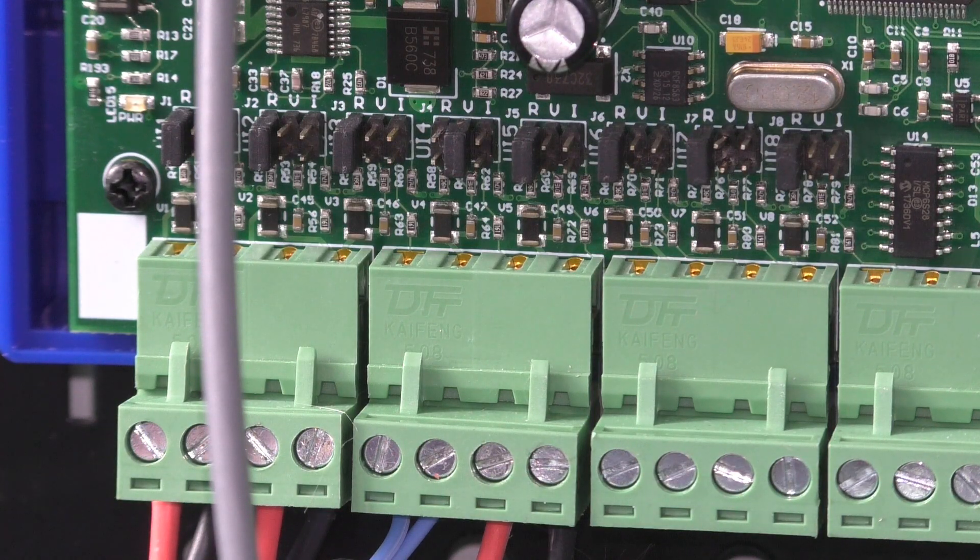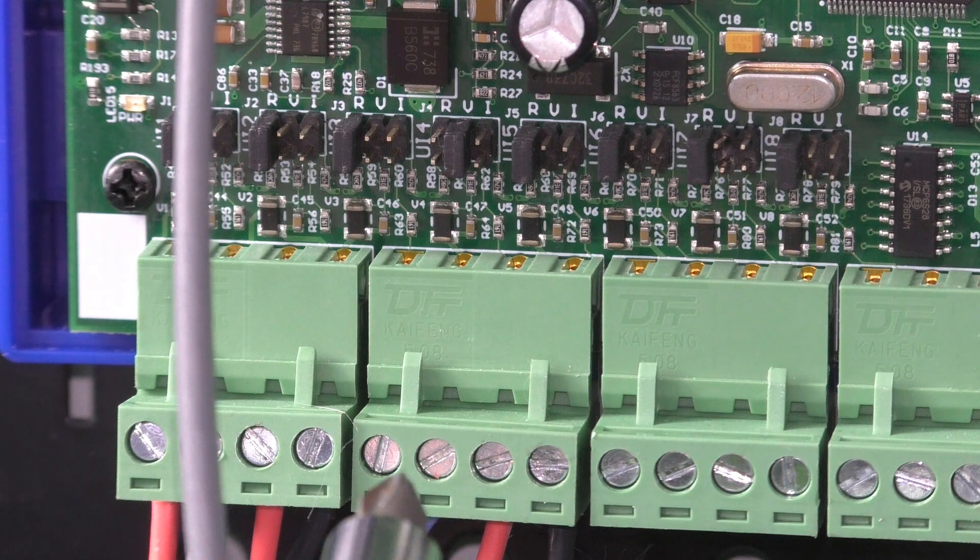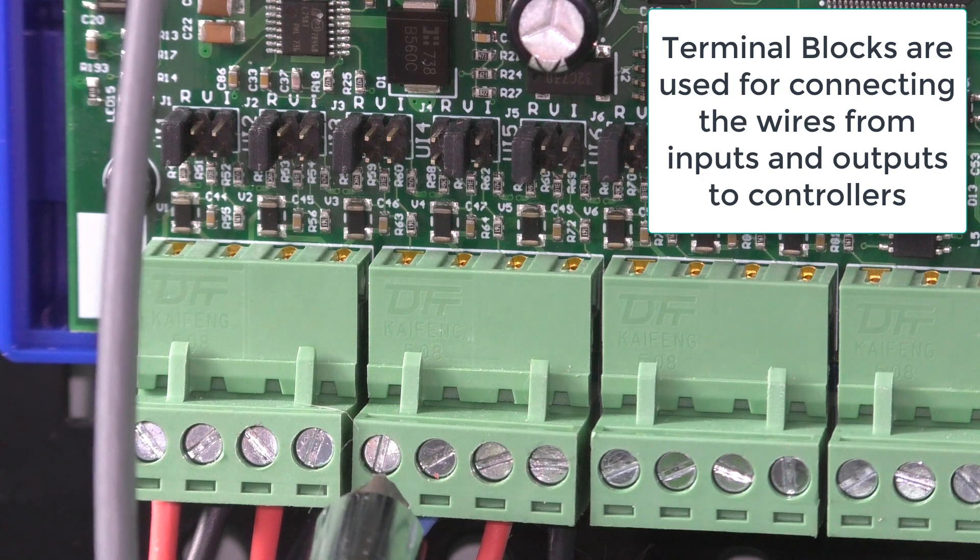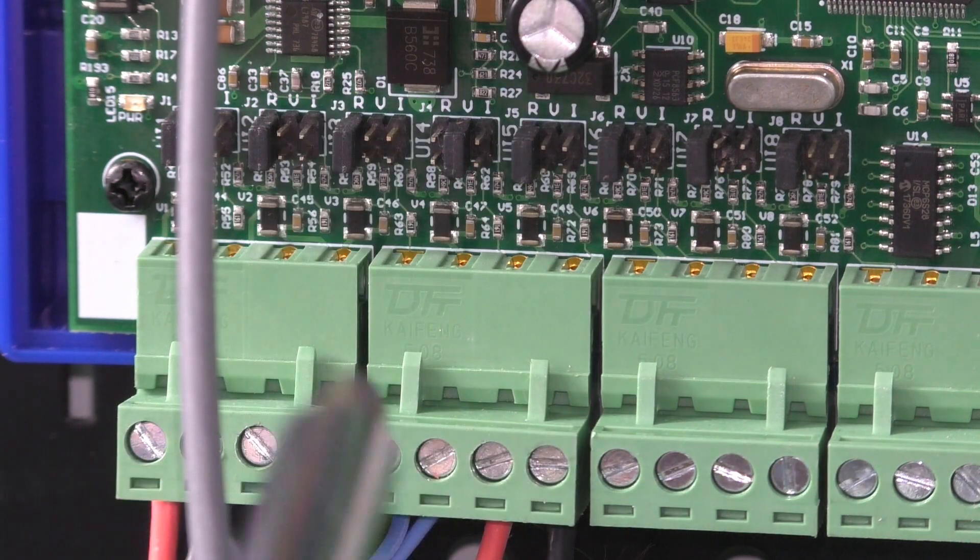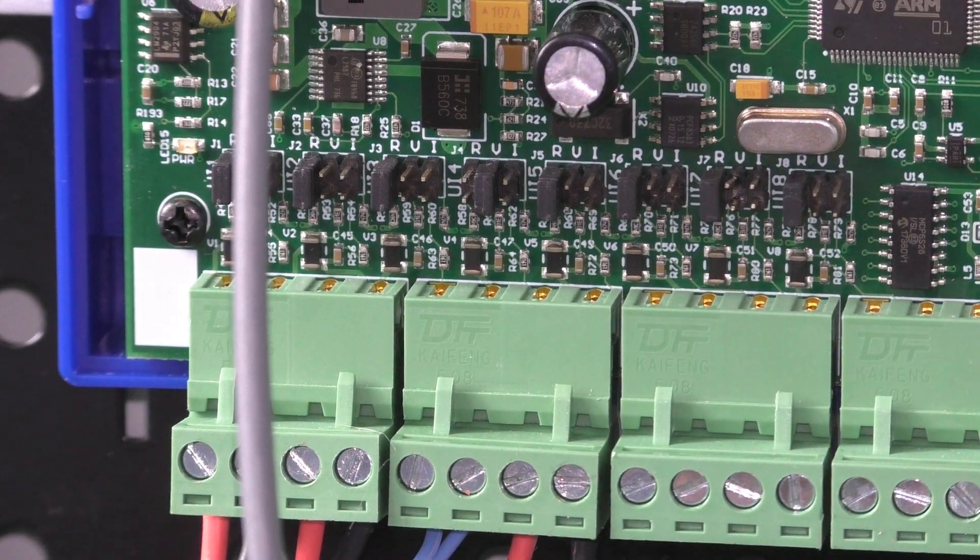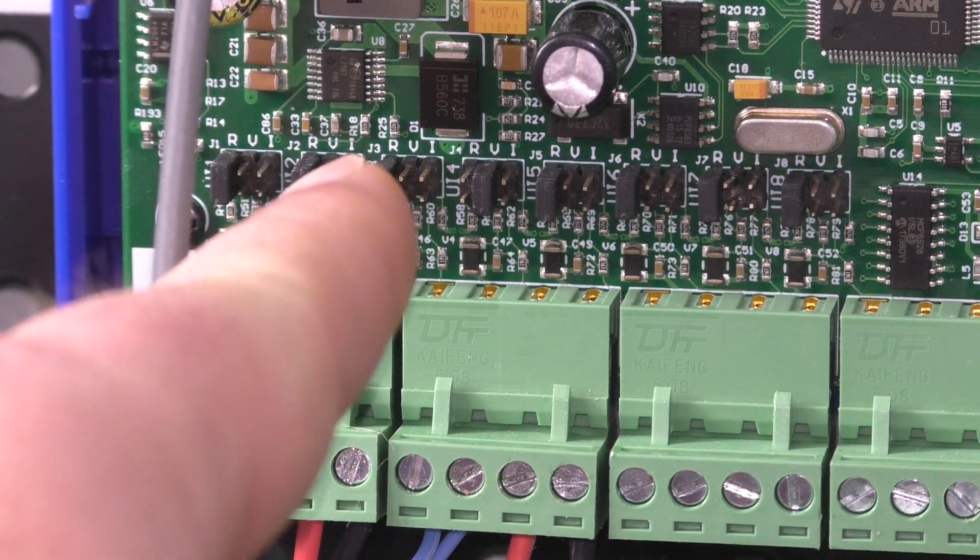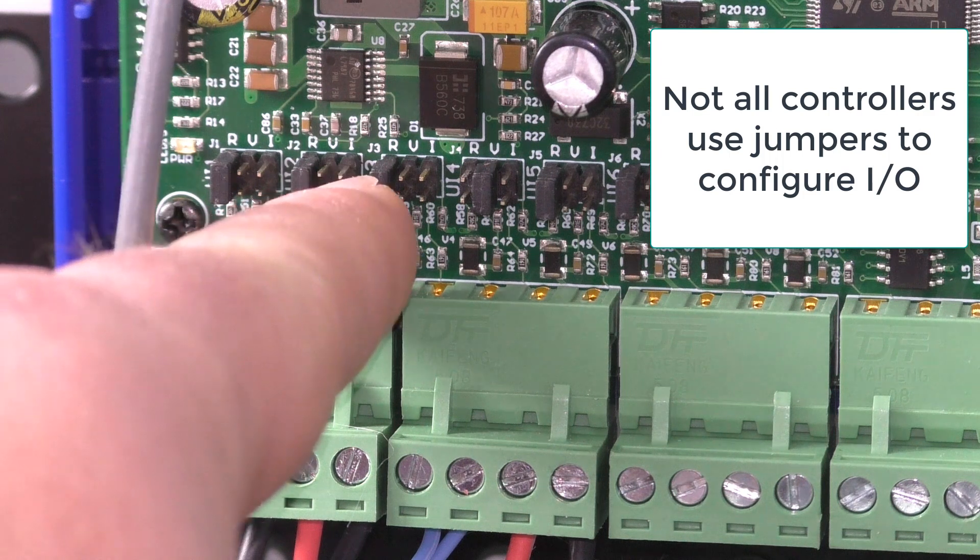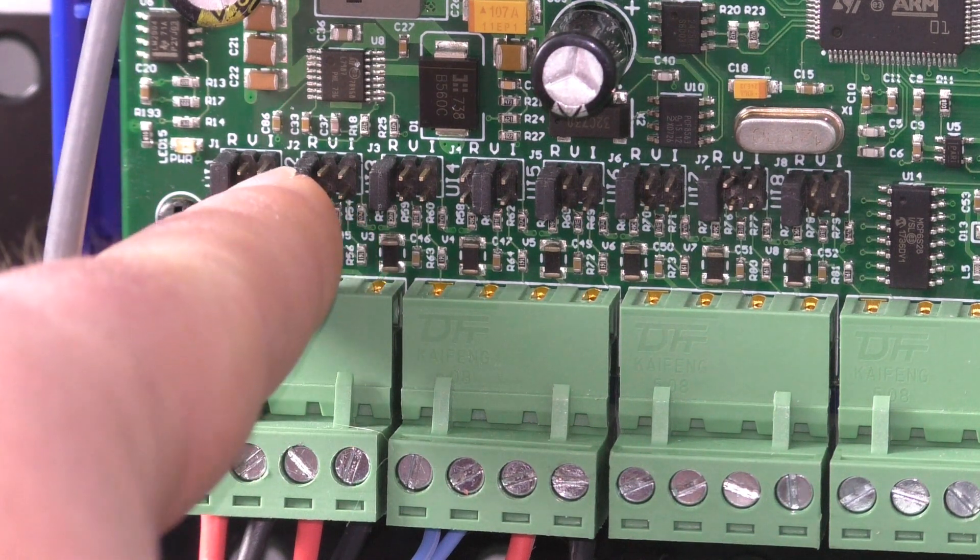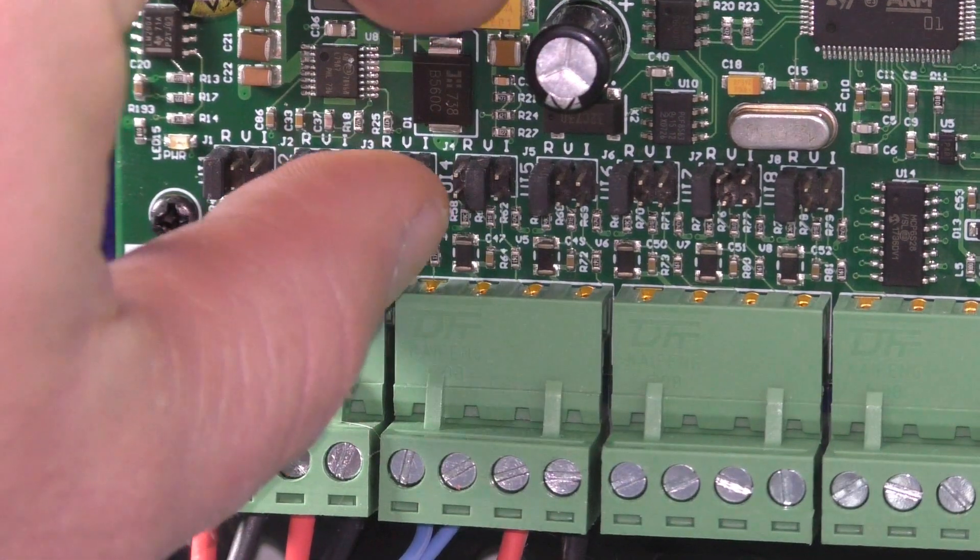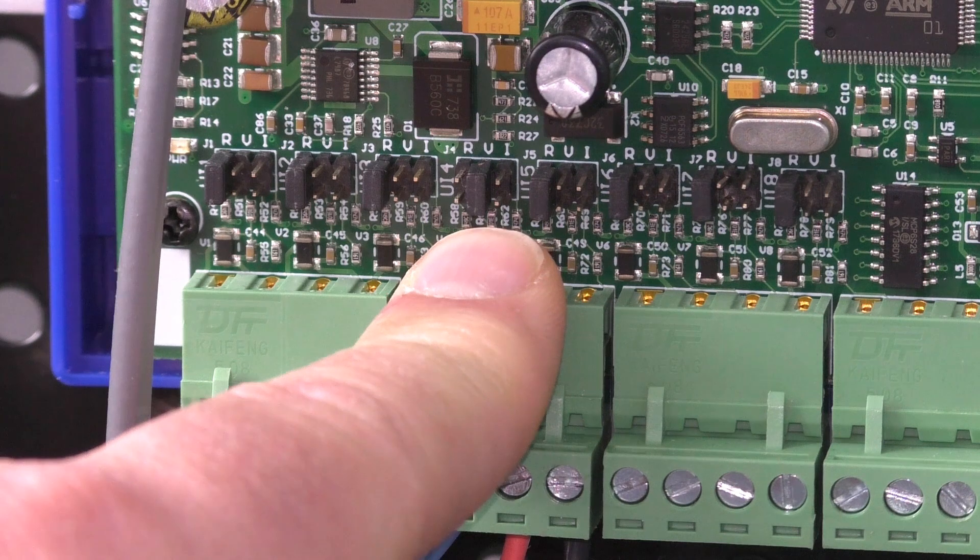What we can see is right here, we've got our terminal blocks. These are where our wires connect to, they get screwed down, you can see right there. The flathead screwdriver will go in and screw it down. We can see over here that we have jumpers. You have an R, V, and I right above the jumper—R is for resistance, V for voltage, and I for current or amperage. If we want to take a resistive input, we would switch it right here. If we want to do a voltage input, we would move our jumper. We can just pull the jumper off and plug it in. You can see I actually did that on this one right here.